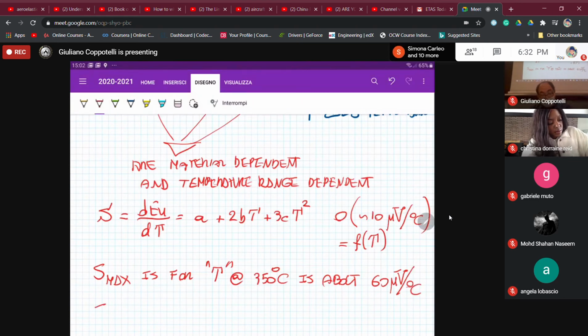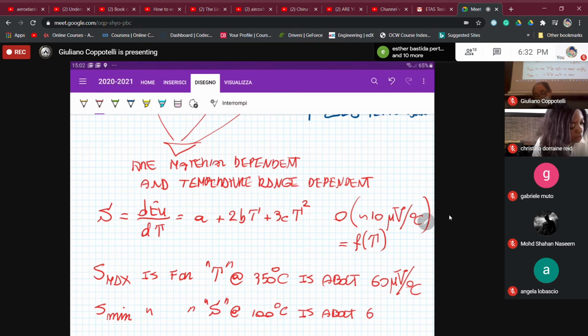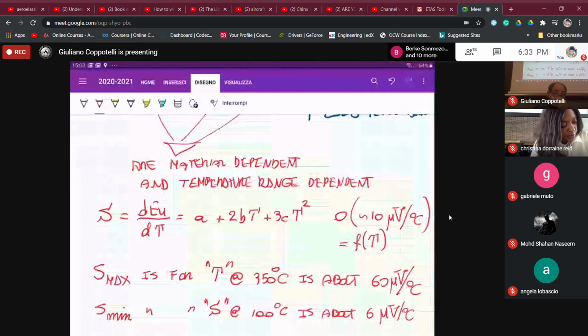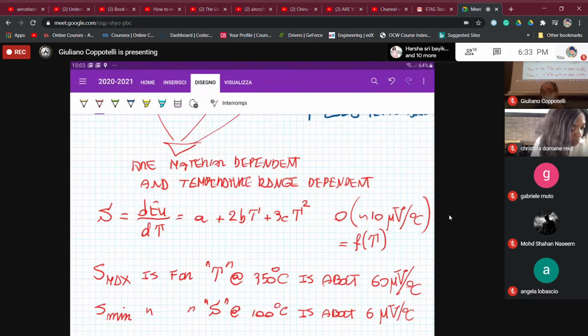The minimum sensitivity is for thermocouple type S, at 100 degrees Celsius, about 6 microvolts per degree Celsius. This tells you the sensitivity range when using different thermocouples. But this sensitivity depends not only on the material type, like T-type thermocouple, but also on the temperature range.